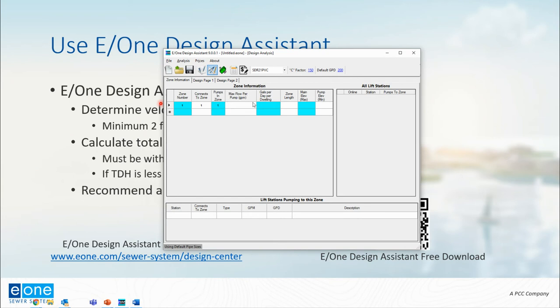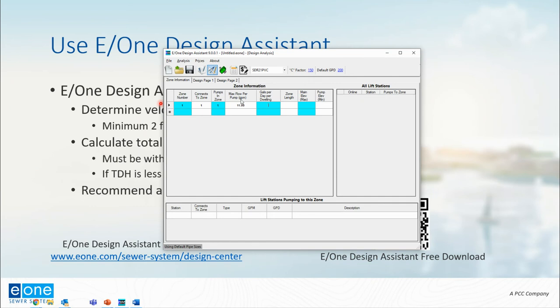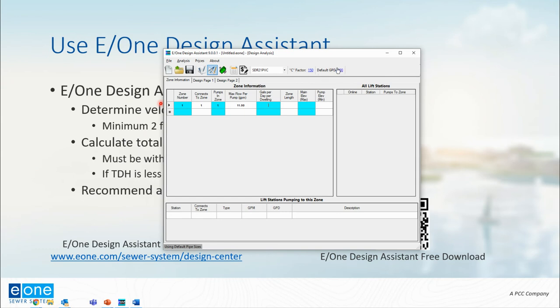It's getting pretty easy here. Maximum flow rate per pump—you can put in whatever you like as long as it's within the capabilities of the E/One pump, or if you hit tab in the software it'll just input a default of 11 gallons per minute, which is about halfway up or about the average of the E/One pump's flow rate. Gallons per day per dwelling, again you can put in whatever you like. There is a default that's shown up here in the toolbar of 200 gallons per day. I can put in whatever I like, or I can hit tab again and we'll put in that 200.